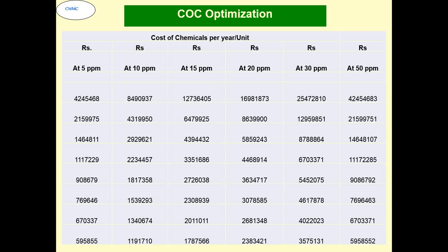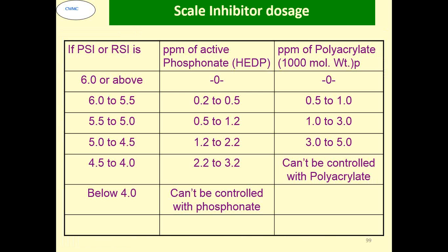This is the cost of chemical per unit that has been calculated. Now this is the generally acceptable levels of dosages. HEDP, which is again a common scale inhibitor, at the RSI of 6 to 5.5, you can go to 0.2 to 0.5, 5.5 to 5, you can go to 0.5 to 1.2. Similarly, at 5 to 4 RSI, you need to do between 2.2 to 3.2 ppm of HEDP.